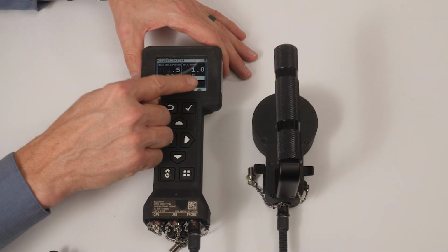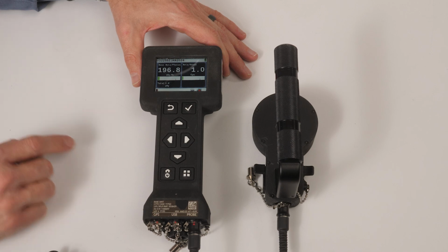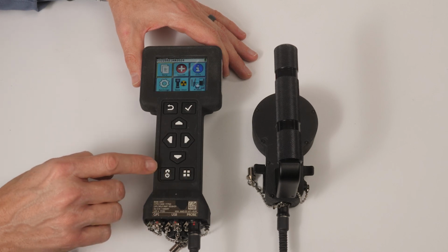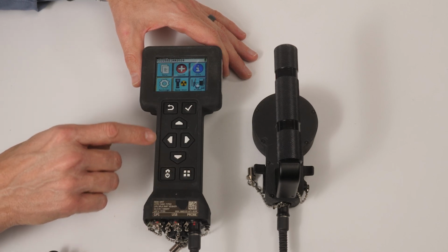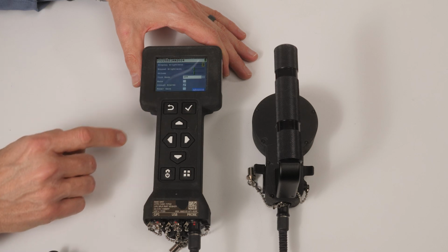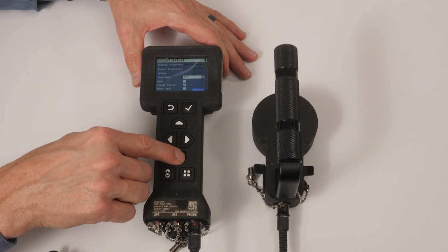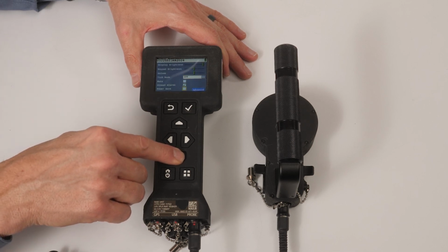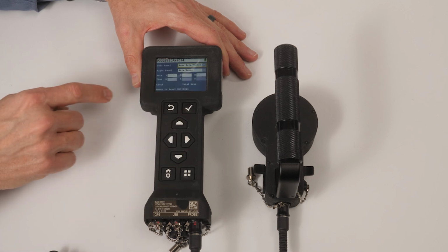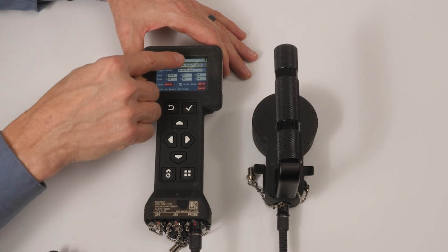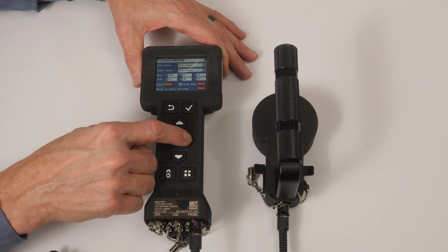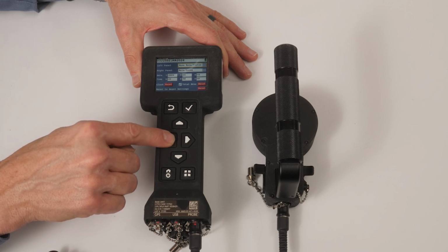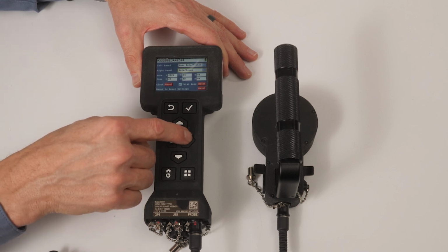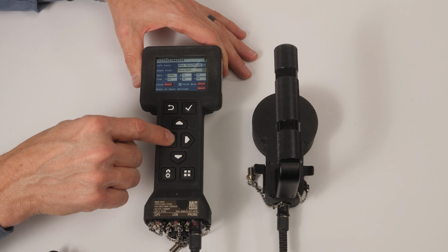Let's go over how to change what radiation readings are displayed in the left and right panels of the home screen. Press the menu key, use the arrow keys to highlight settings, and press the Enter key. Use the down arrow key to highlight the Advance button and press the Enter key to select it. The operator can choose what radiation readings to display in the left panel or the right panel on the home screen. Use the right and left arrow keys to change panel options.